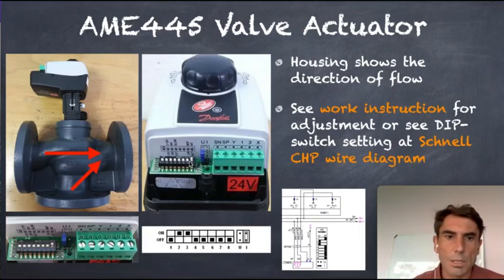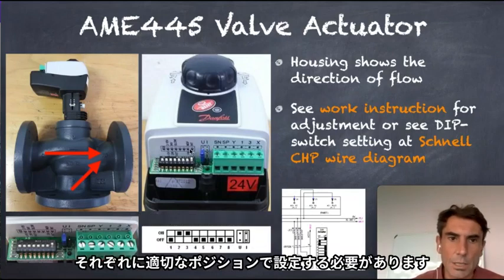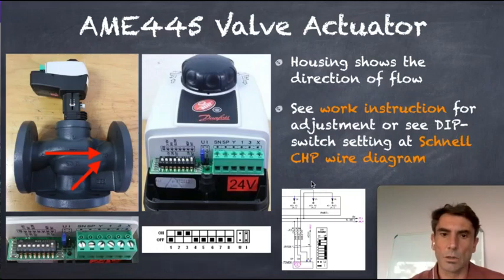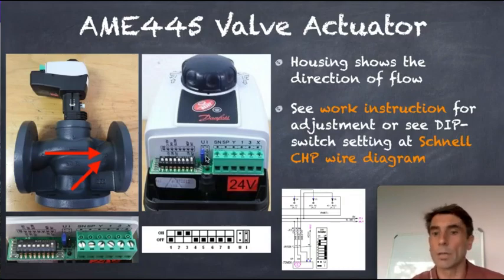There's a screenshot from a wire diagram of one of the Schnell CHP, and there we can see as well how the dip switch must be set, and here is a bridge connector that adjusts if this motor is operating on voltage, so U, or it's operating on current signal, so I, and this switch actually adjusts what kind of signal is used and how the motor operates. So always ensure that these settings and this bridge are right or connected right.